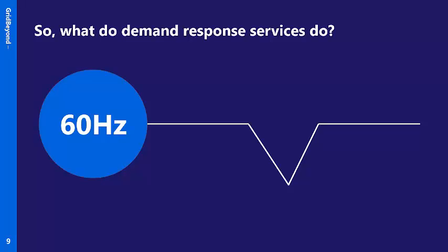So the way that the electricity system is measured in terms of its balance is a perfect balance of the right amount of power generated, supplied, versus the exact amount of power consumed. Means that in the US terms, to do that, the system will be sat at a very nice 60 hertz. It's never the case. It passes through 60 hertz on a very regular basis, but effectively frequency on the system bounces up and down every second and down to the millisecond, and that's because maintaining that perfect balance of the amount of power generated versus the amount of power consumed is obviously incredibly difficult.